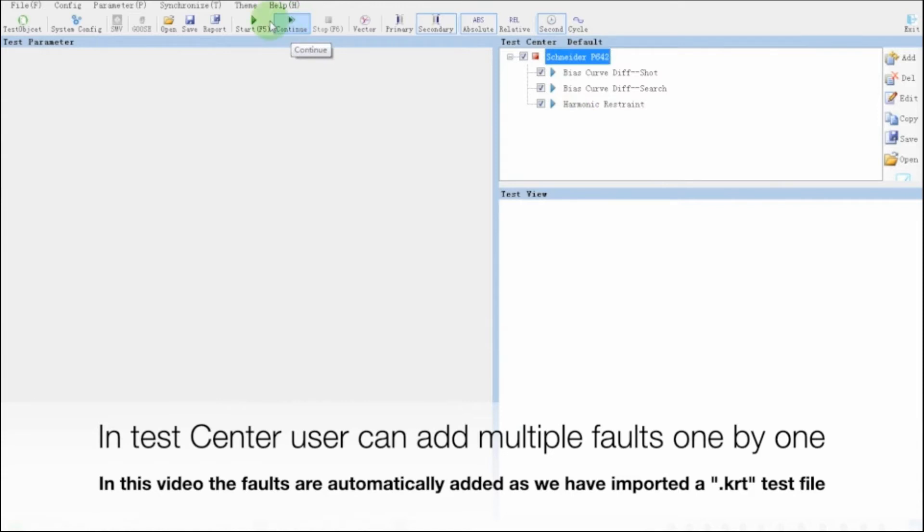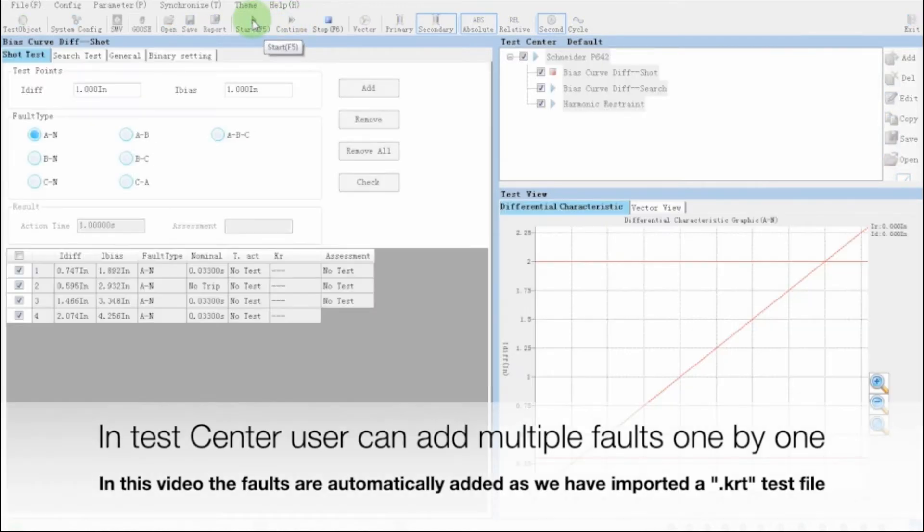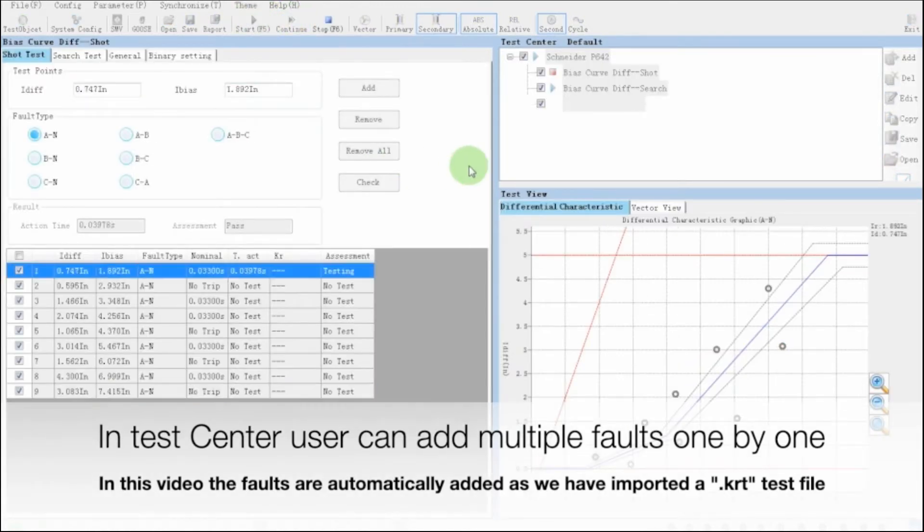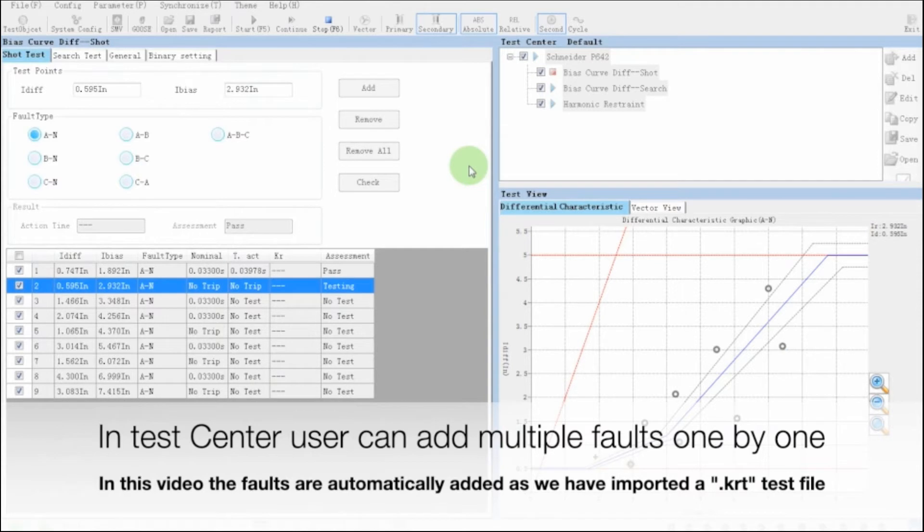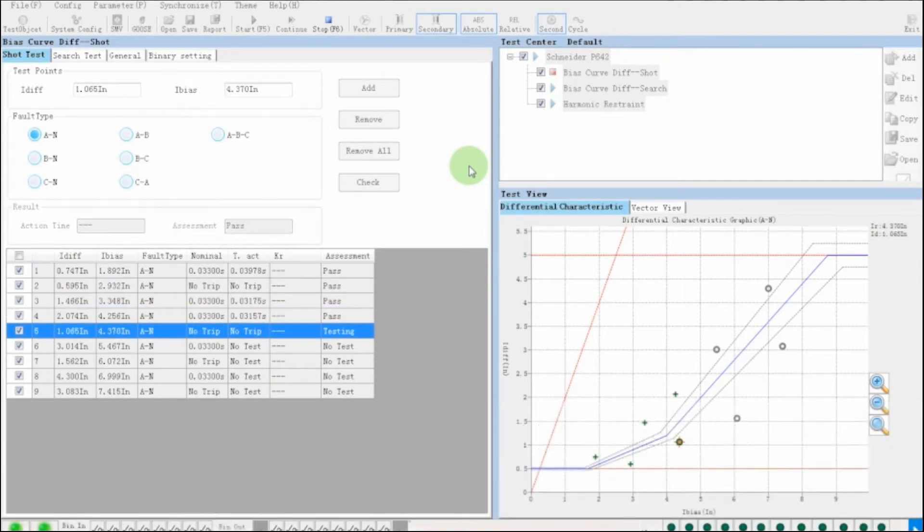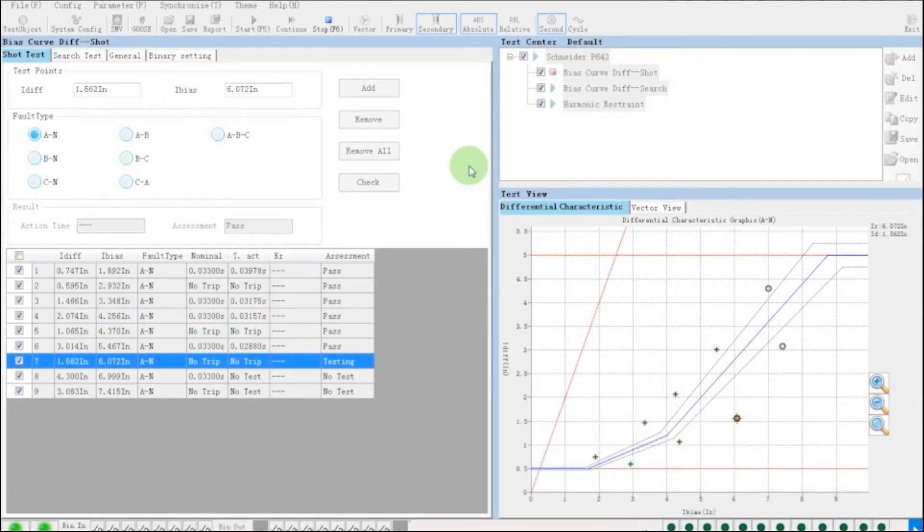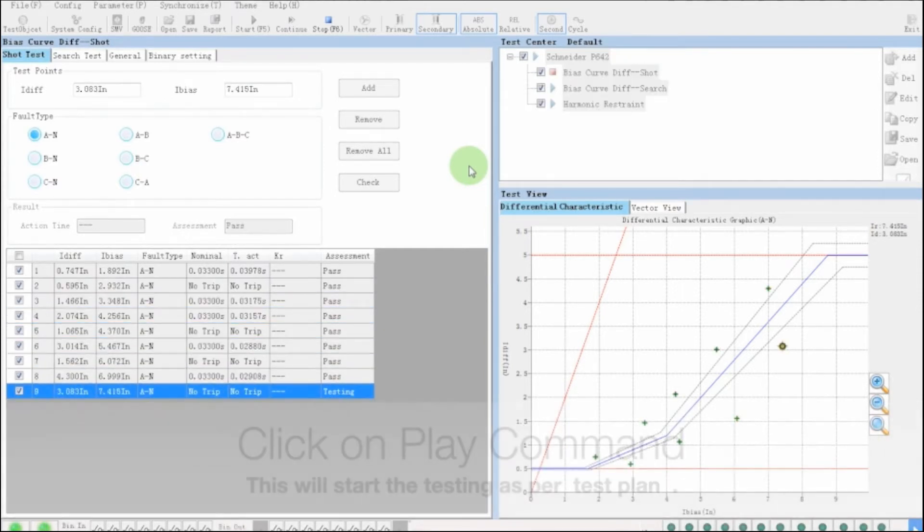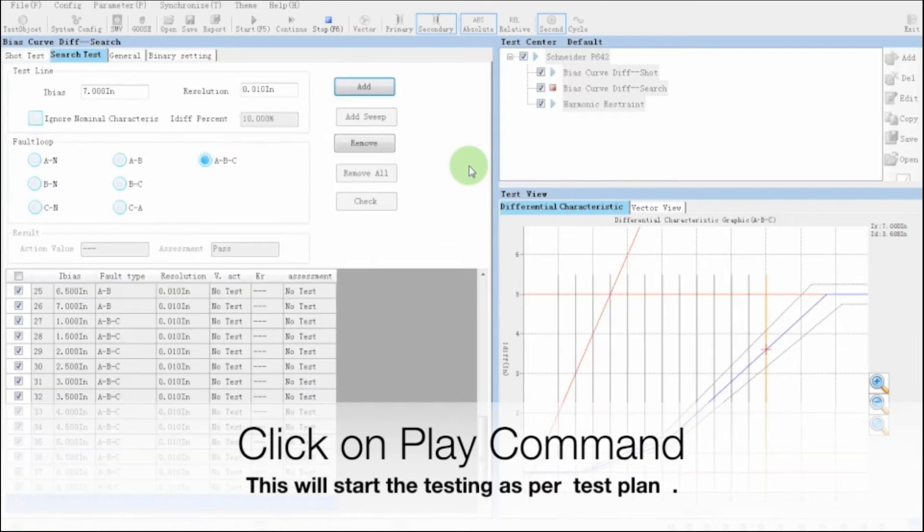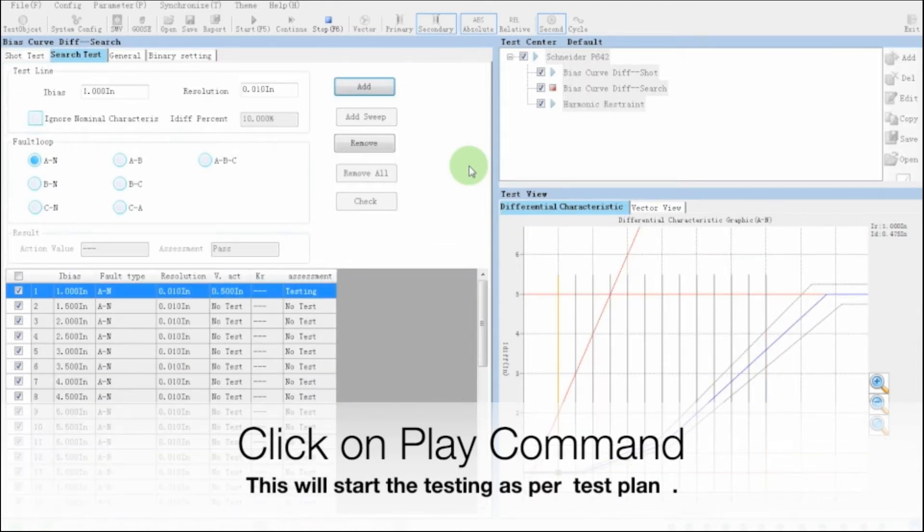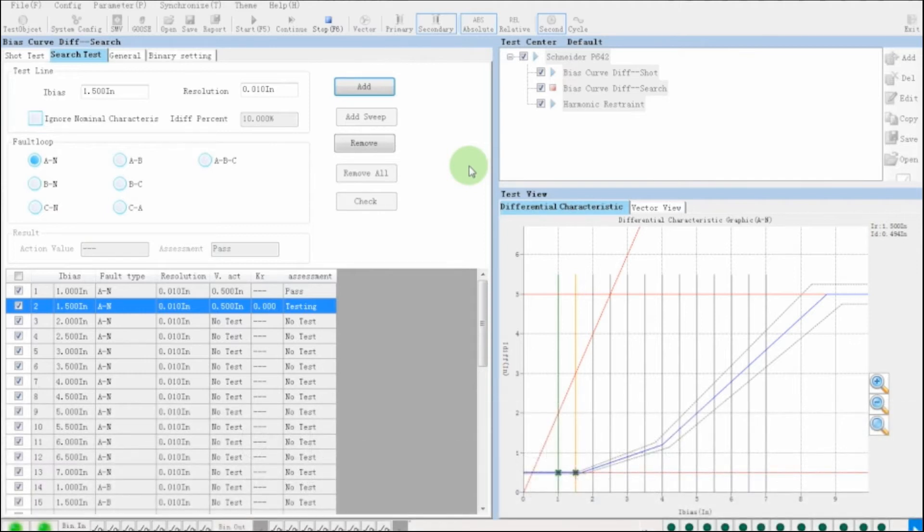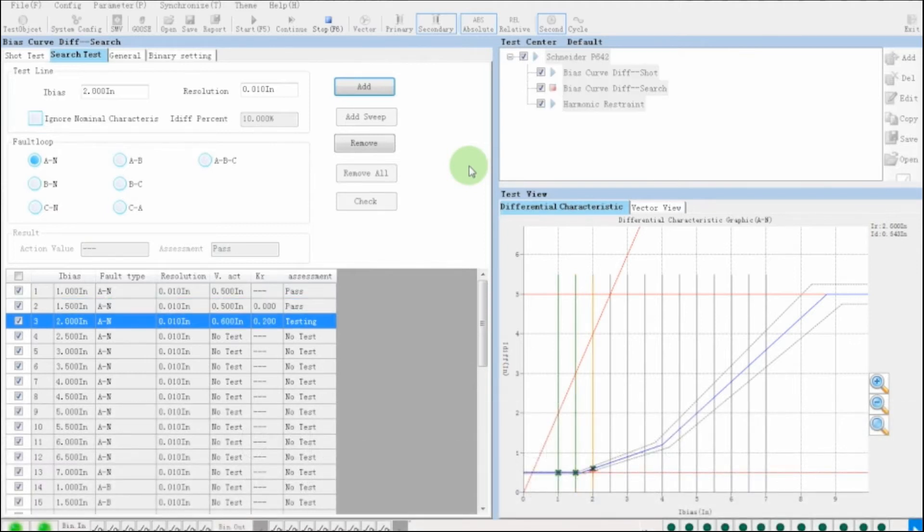We can clearly see in test center window, user has selected three test models to run automatically one by one. So we just have to press on play command. The relay test kit will automatically test all the faults in bias curve shot model, and then in bias curve search model, and then in the harmonic restraint model.